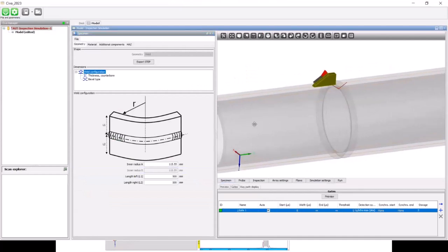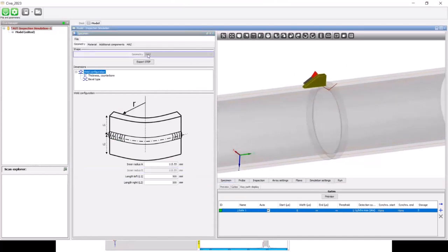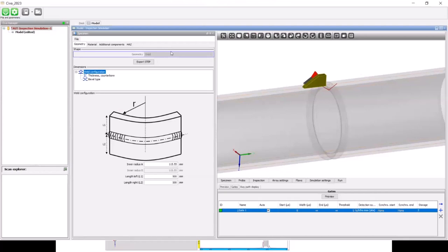For those who know CIVA UT, it's pretty similar. You have a graphic representation of a component — in this case a pipeline and a weld — a probe, and different panels at the bottom to define your own parameters, usually from left to right. In the specimen panel, you can only define girth weld, which is represented here. In the full CIVA UT you have other component types, but we dedicate AUT pipeline to girth weld inspection.